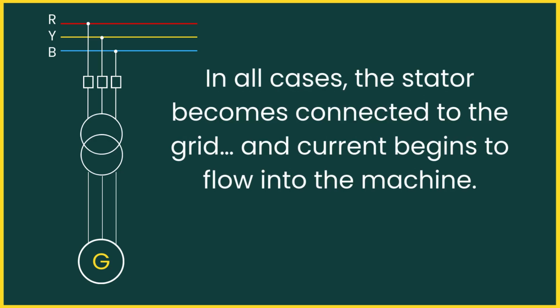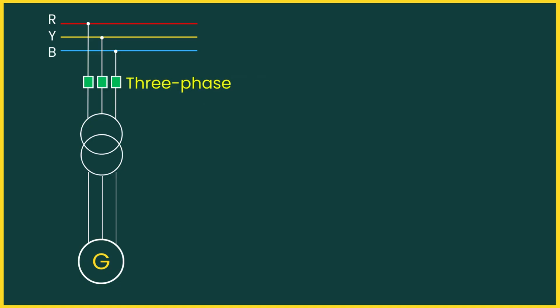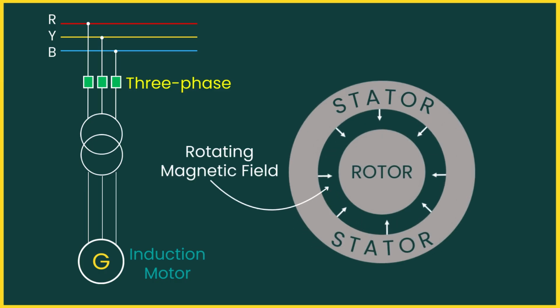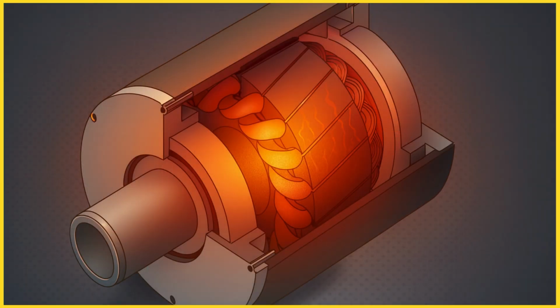The generator may be energized either on all three phases, or two-phase, or on just a single phase. In all cases, the stator becomes connected to the grid, and current begins to flow into the machine. If a three-phase voltage is suddenly applied to a stationary generator, it behaves like an induction motor. A rotating magnetic field is created at synchronous frequency, inducing heavy current through the rotor body and damper windings. The first effect: rapid surface heating in the rotor iron, especially around the wedges, retaining rings, and rotor body. If protection does not act quickly, this heating can lead to severe rotor damage.